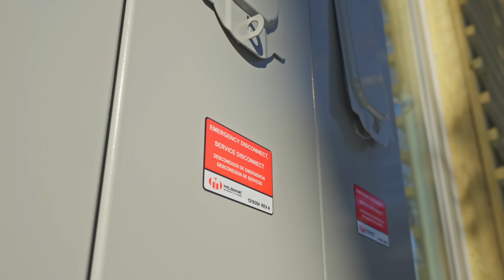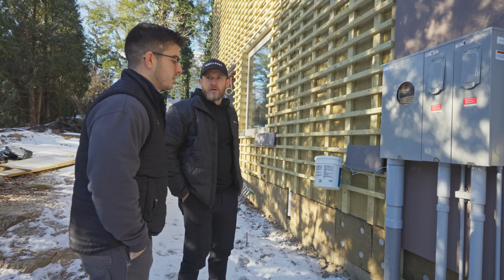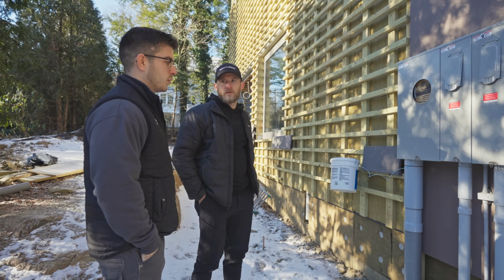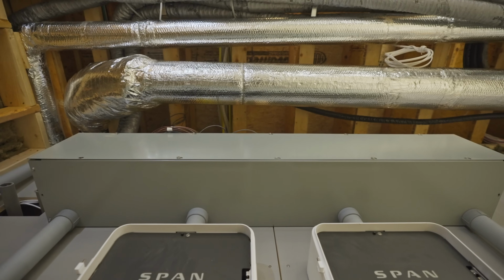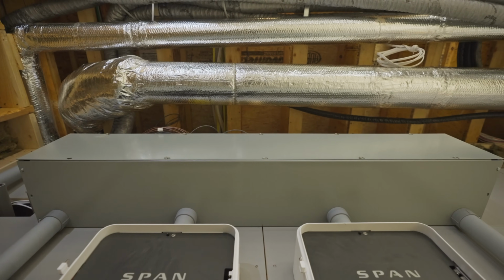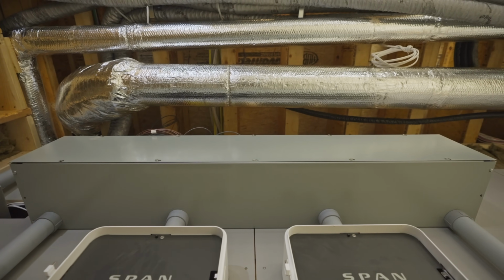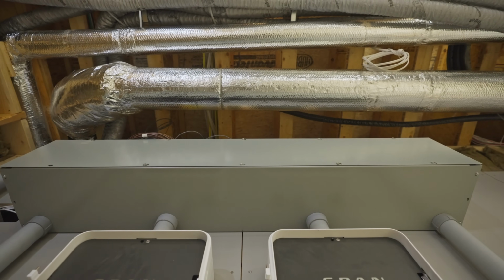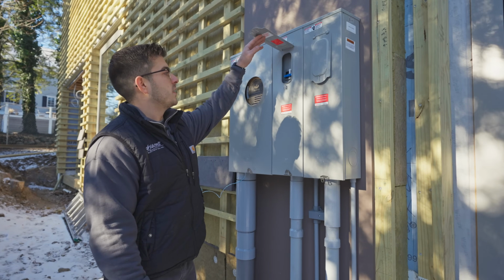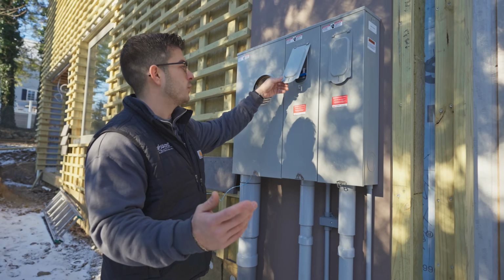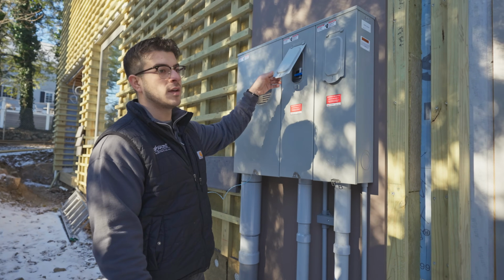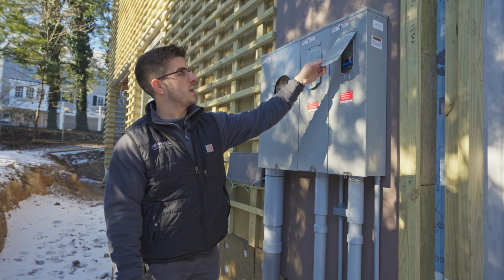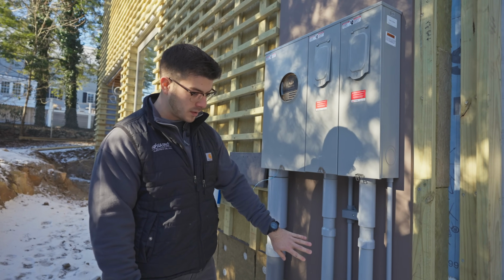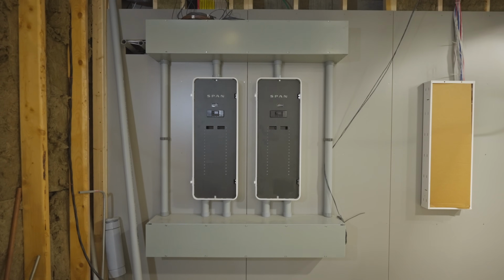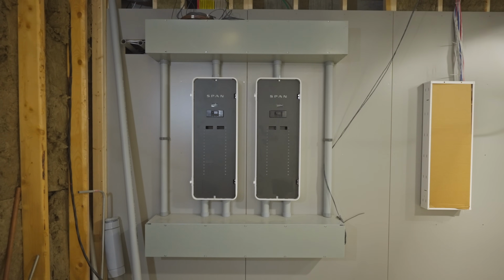Why do we have two of them? We have two emergency disconnects because the span panels are only rated for 200 amps, so we had to take our 400 amp main and split it into two 200 amp feeders going in to feed the panels individually. Under the new code, our main disconnects have to be outside, as opposed to a few years ago when they could be inside. So we have two 200 amp mains that are individually piped down through the foundation into our trough, which will individually feed our two panels downstairs.